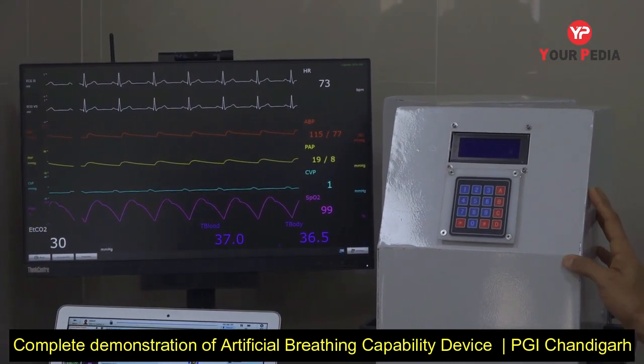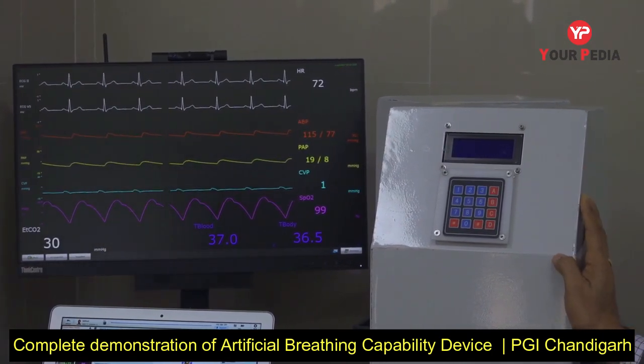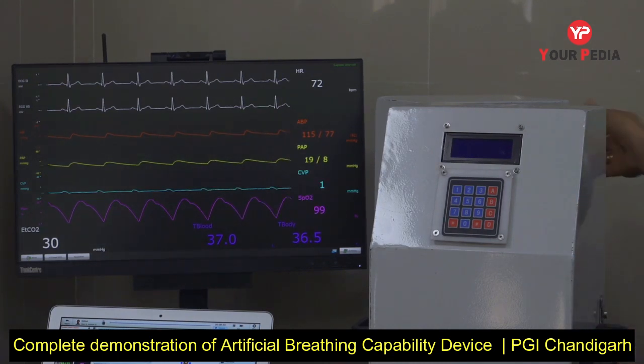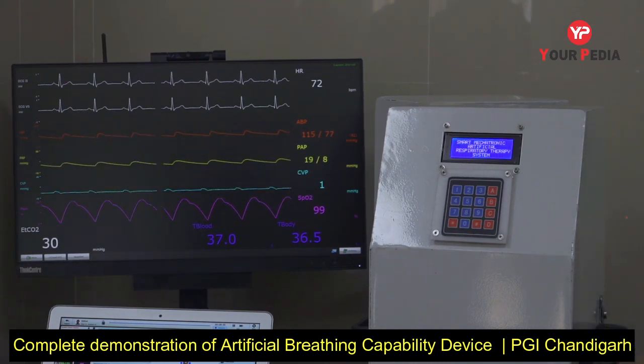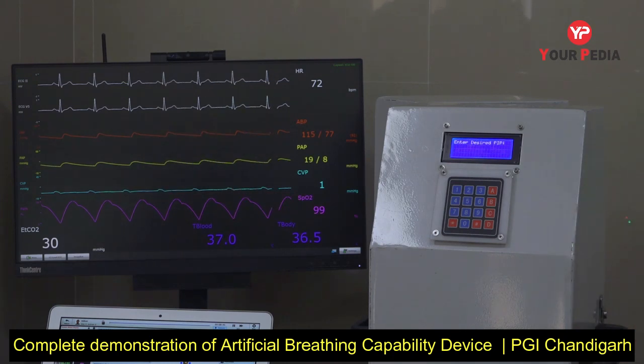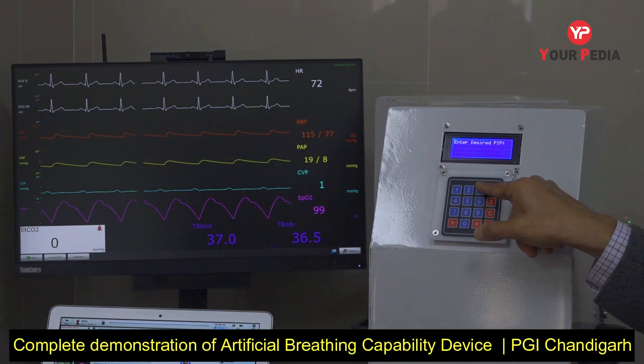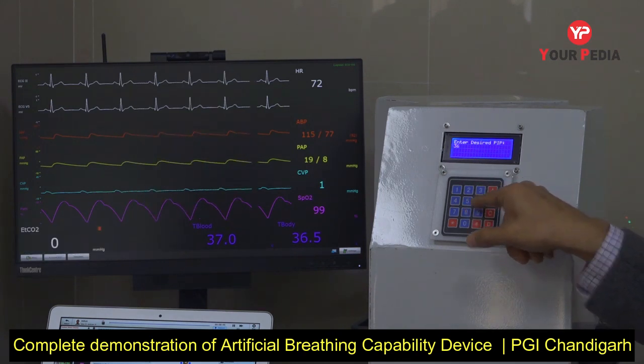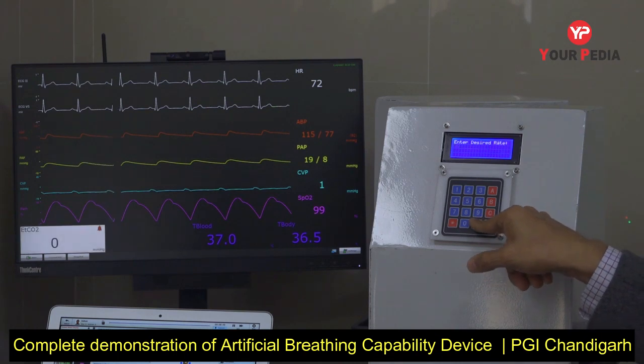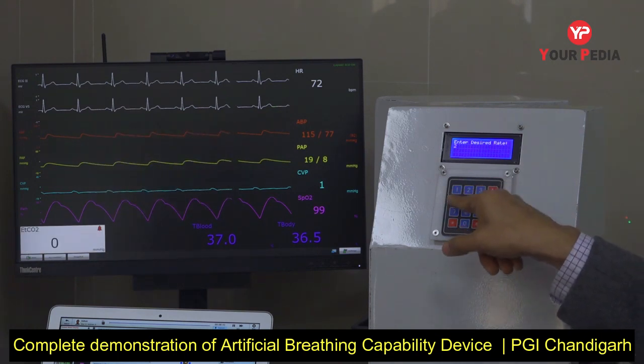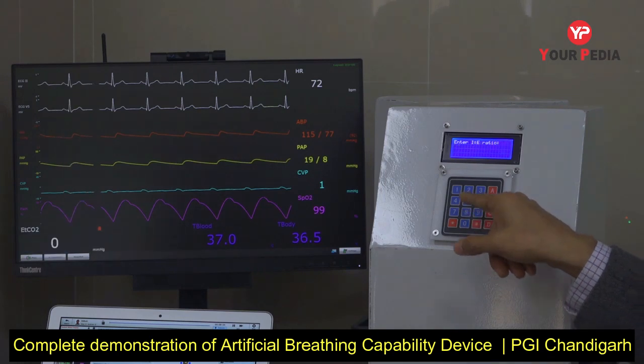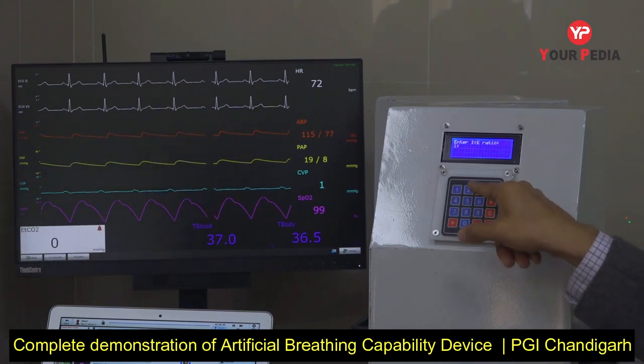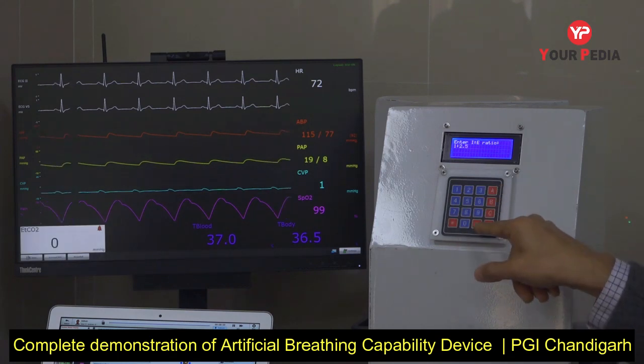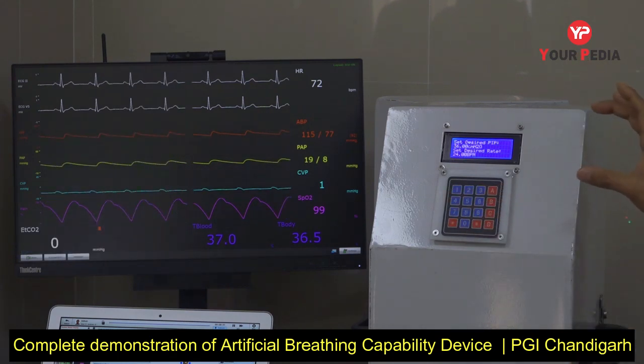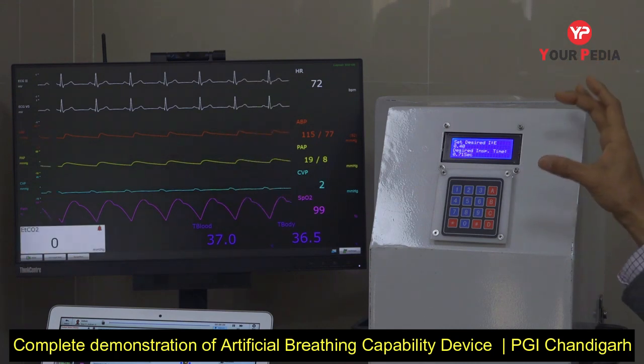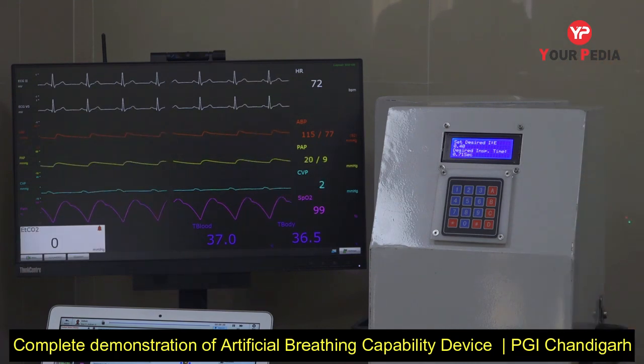Meanwhile, we will now simulate a patient who's got damaged lungs and requires far higher pressure. So I switch on the machine again. The machine does its own self-check and then allows me to enter the desired pressure. This time I'm going to enter a pressure of say 36, which is a reasonably high pressure. We set that. The desired rate is going to be set at 24, which is a higher rate, and I'm setting an inspiratory to expiratory time ratio of 1:2.5. So the machine performs its own self-checks. It shows us on the screen what we set it as and immediately starts responding.